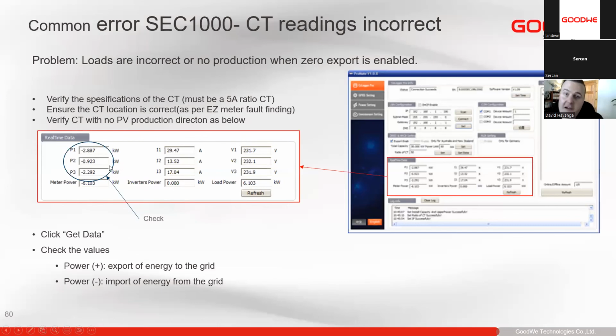So same with our smart meter CTs. If you are using CTs, please try not to use cables longer than 5 meters. 15 meters normally is the maximum. If you run it any longer, you need to make sure you have special CTs that can cater for that. But I would never advise running long CT cables. It does affect your accuracy and efficiency. The RS485 cable can be extended very long, so it's better to install that a kilometer away and run your CT cables as short as possible for higher accuracy.